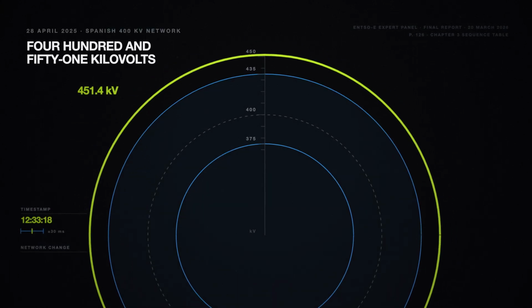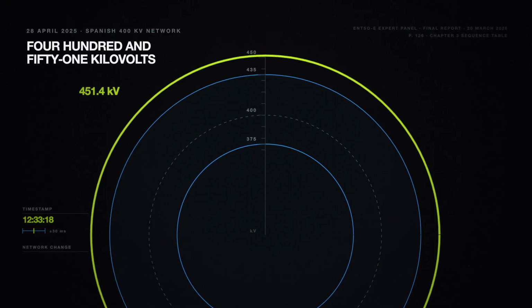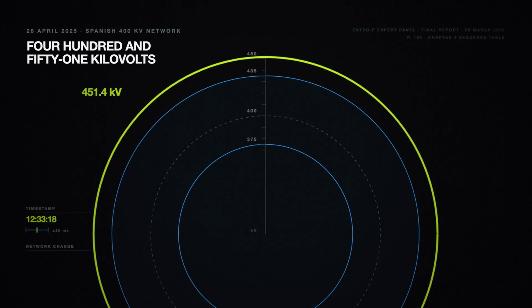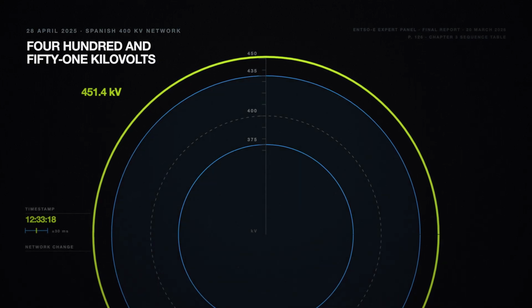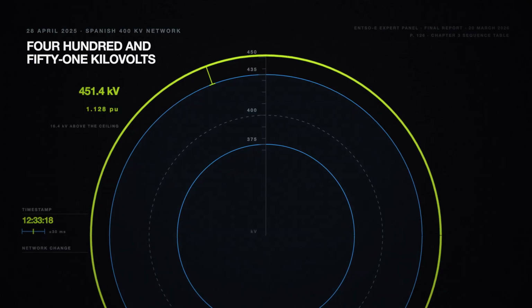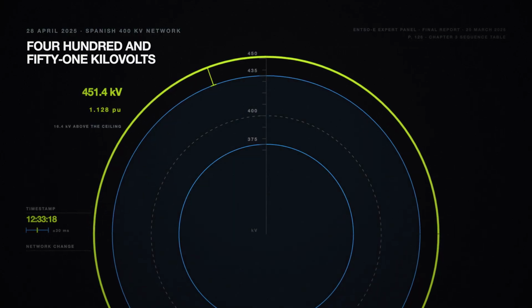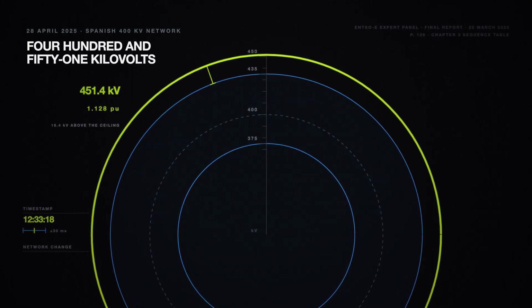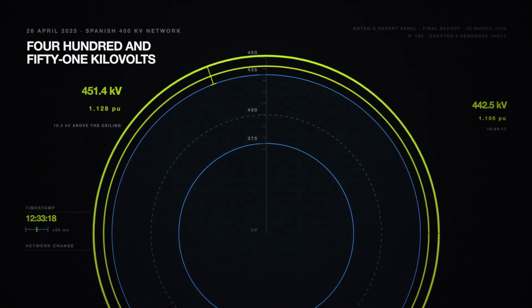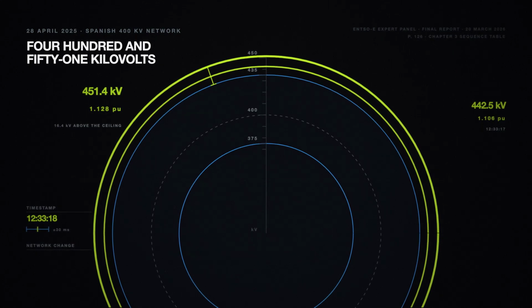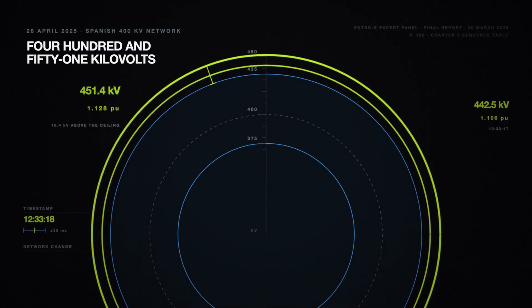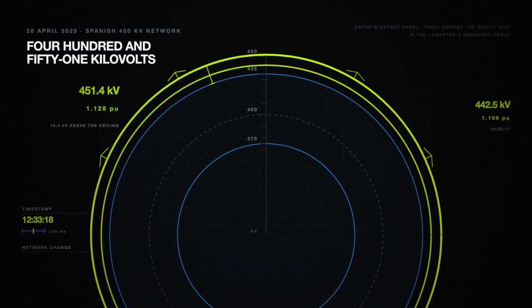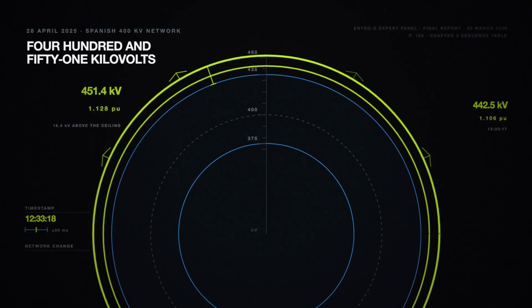12:33 and 18 seconds on the 28th of April, 2025. 451.4 kilovolts on a network built for 400, 1.128 per unit. The admissible range for the Spanish 400 kilovolt network is 375 to 435 kilovolts, and that reading sits 16 kilovolts above the top of it. A second earlier, the same network was at 442.5 kilovolts, 1.106 per unit, already outside. The voltage was not falling. It climbed through the last seconds the Iberian Peninsula had power.